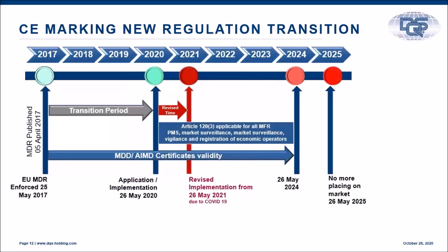After that, there is a further period under the regulation to place the product into the market for 1 year. What placing the product in the market means is the product needs to be put in use before 26th May 2025. That means if there is a product which needs installation, that installation activity needs to be completed before 26th May 2025.